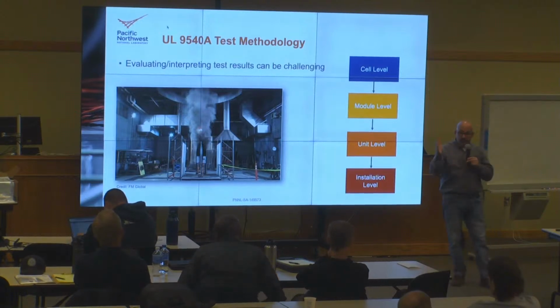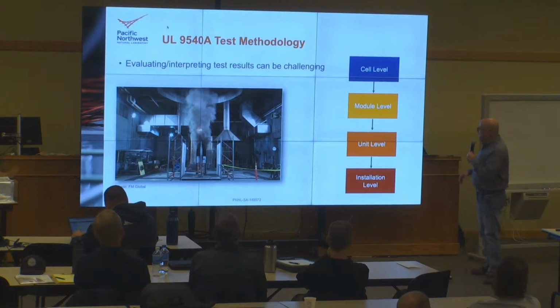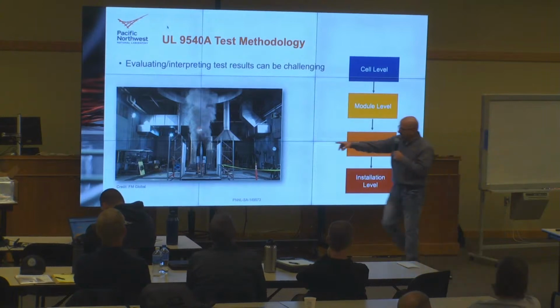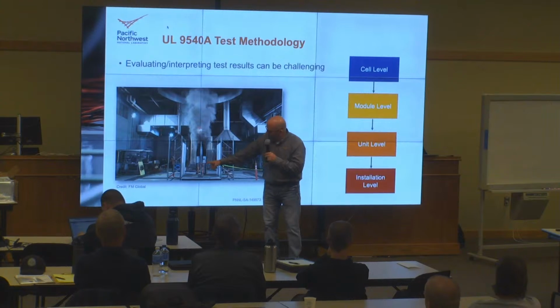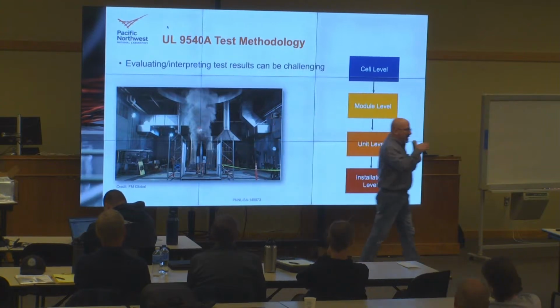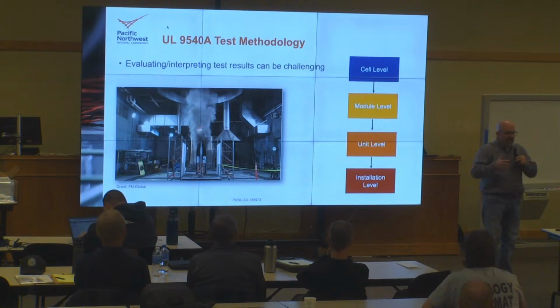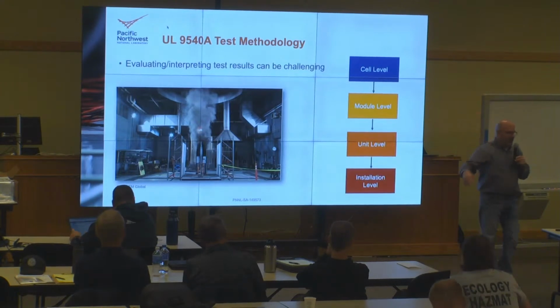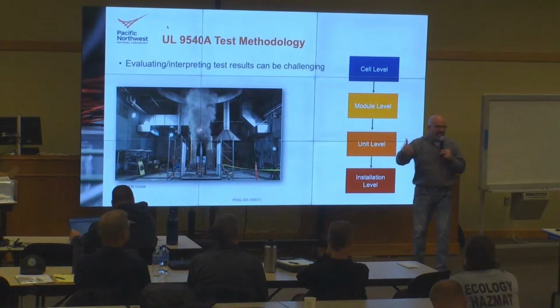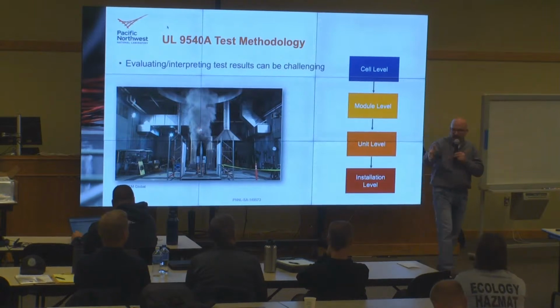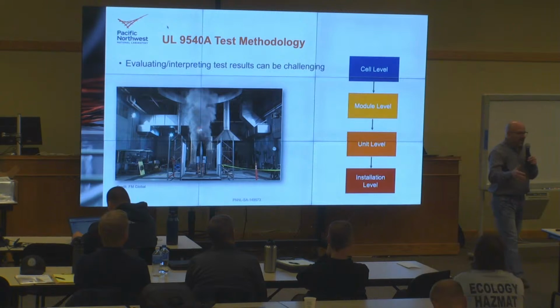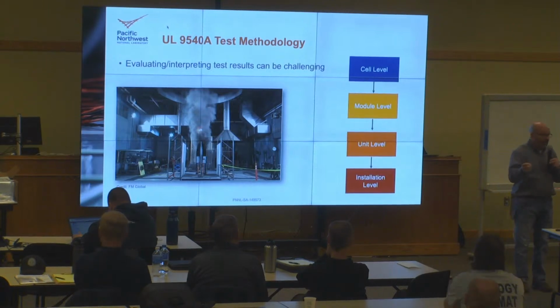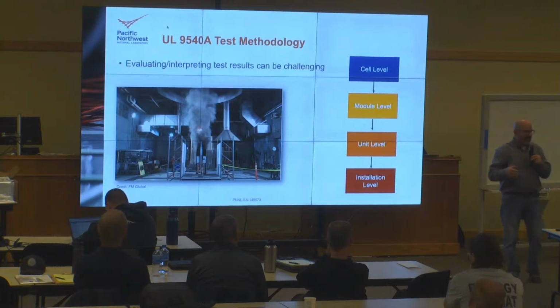The unit level test is what we're seeing right here, a whole bunch of modules, and the goal is to see if you can get fire outside of that unit. If you do, then you go to the installation level test, which requires a fire suppression system, because the goal is not to have propagation to the next unit. Even though, as I mentioned, there's not really good fire suppression, if you're having flames come out, those flames could be suppressed by an agent, but it's limited in its effectiveness.